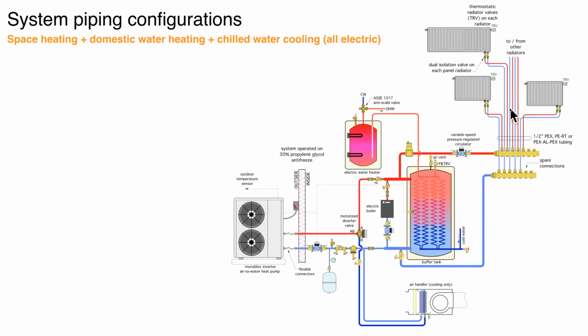But remember, this could be multiple zones of radiant panel heating, or it could be a combination of panel heating, panel radiators, maybe even a fan coil. So the home run approach is a very flexible approach in terms of combinations of heat emitters. This circulator can adjust its speed based on what the fluid demand is out here.